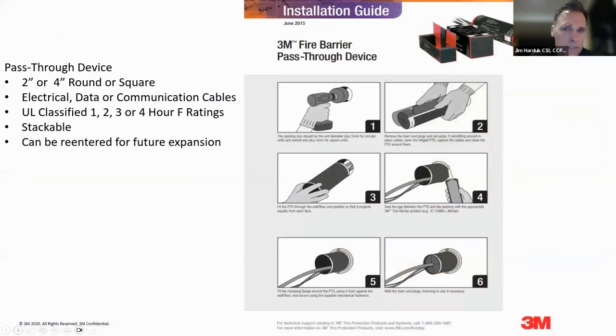Next slide. Here's an example of an installation guide. As with all of the 3M fire protection products, we have installation guides available. They're typically set up in the same format where it's a pictorial, minimal text on there. So, the intent here is that if you had a multilingual trade force and they were trying to determine how to install this, they could pretty easily just look at the picture and get a general idea on how this material would get installed. The pass-through devices, we have a few different hourly ratings available, so we have a few different tested configurations for this product as well. Next slide.